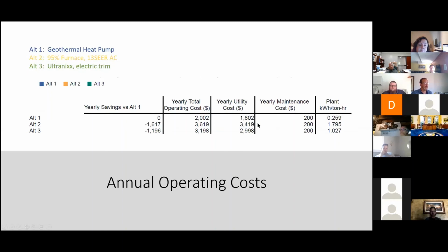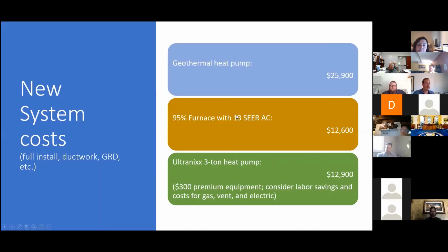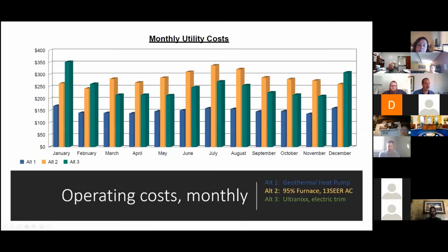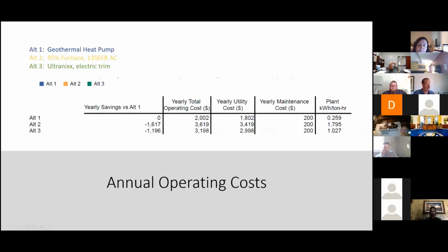The cost to operate that furnace and air conditioner over the course of the year, $3,400. And our Ultranixx heat pump with electric trim heat is a little bit less. You can see that it makes sense that his geothermal heat pump is operating at about half the code requirement. So unfortunately, you know, that is not always available for everybody. This gap is available, and there is a payoff in it.